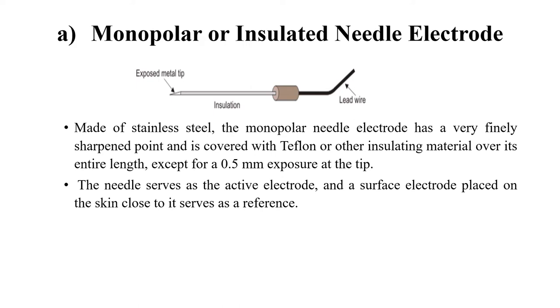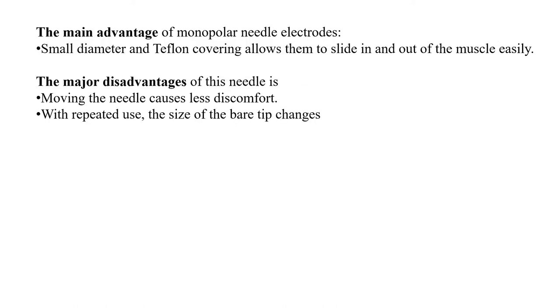The figure shows the monopolar needle electrode, also called the insulated needle electrode. It consists of a solid needle made of stainless steel with a sharp point. The shank of the needle is insulated with a coating of Teflon or other insulating material, covering its entire length except for 0.5 mm of the tip, which is left exposed. A lead wire is attached to the other end of the needle, and the joint is encapsulated in a plastic hub to protect it. The needle serves as the active electrode, and a surface electrode placed on the skin close to it serves as the reference.